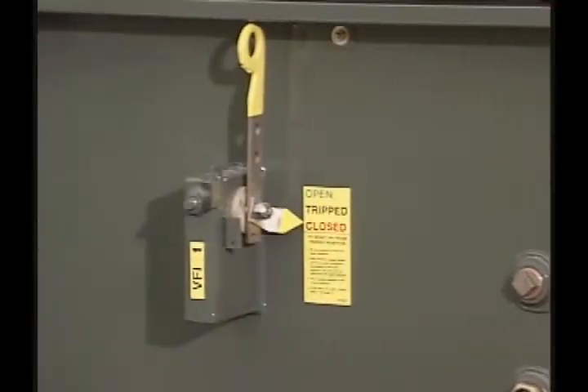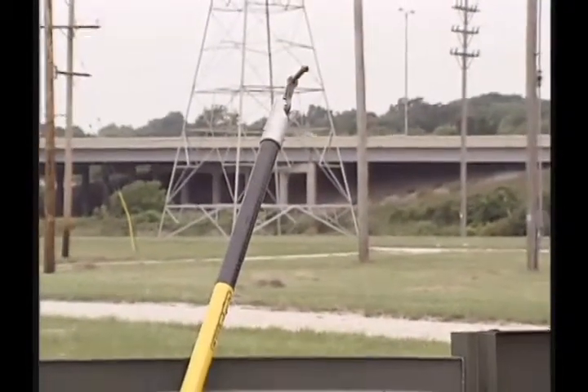When operating and testing this equipment, follow all locally approved procedures and safety practices. The VFI can be manually operated for load break, load make switching using the operating handles. The VFI push-pull operating handles must be operated with a hot stick.